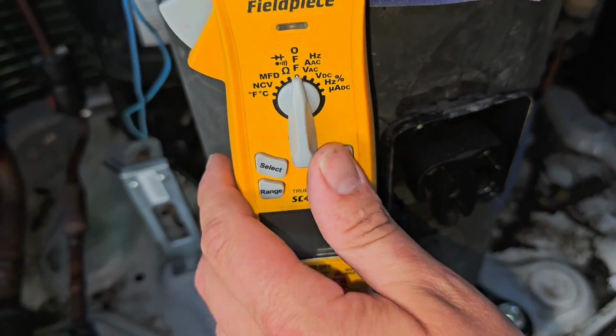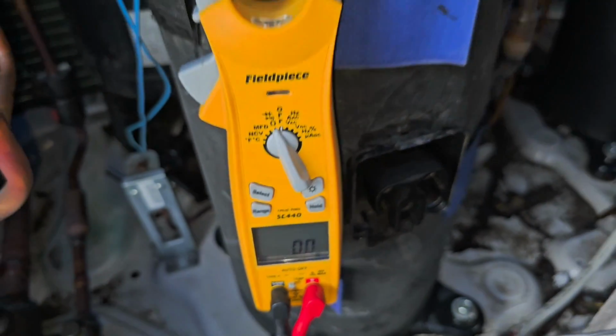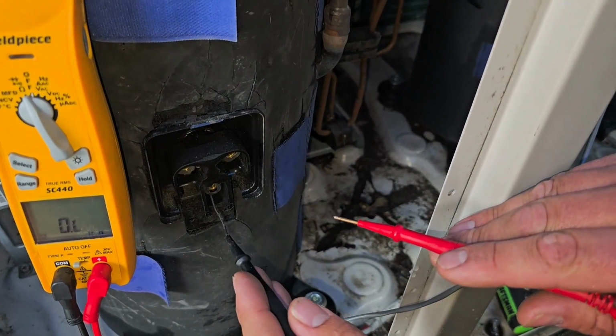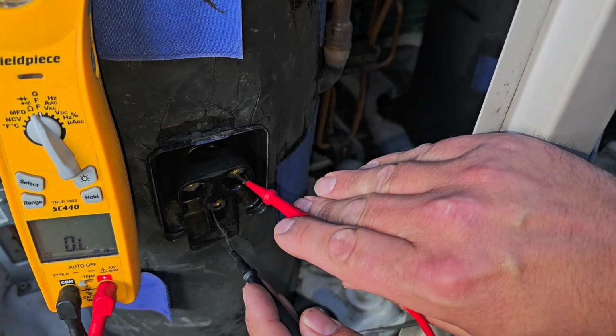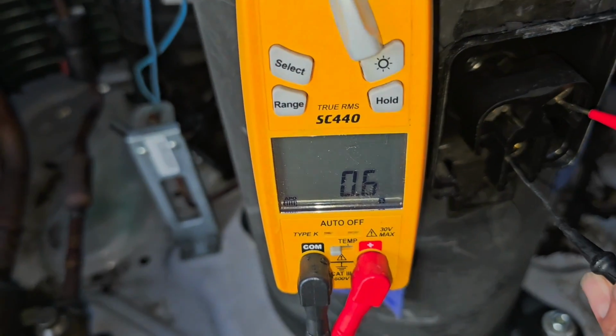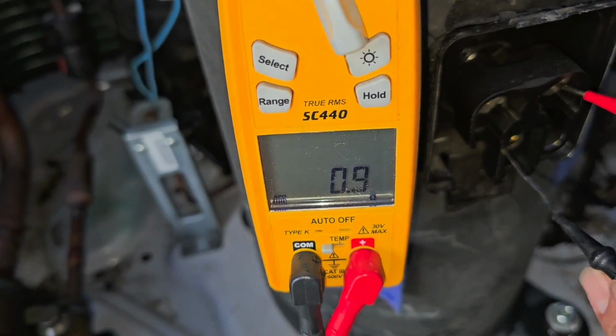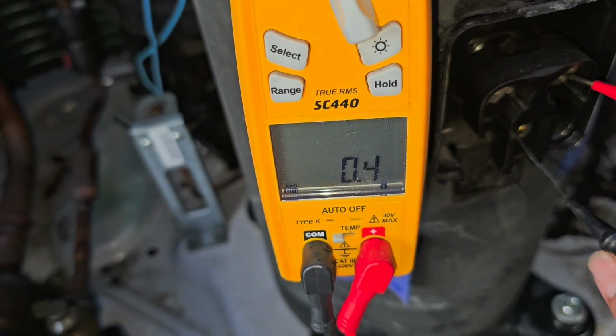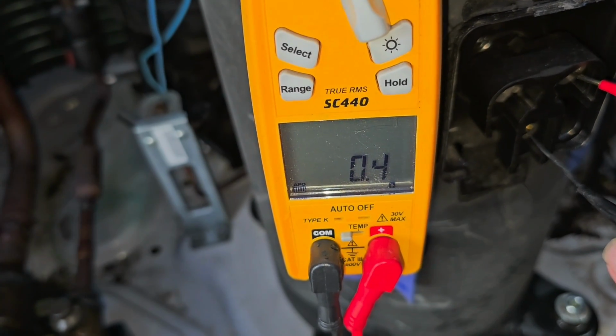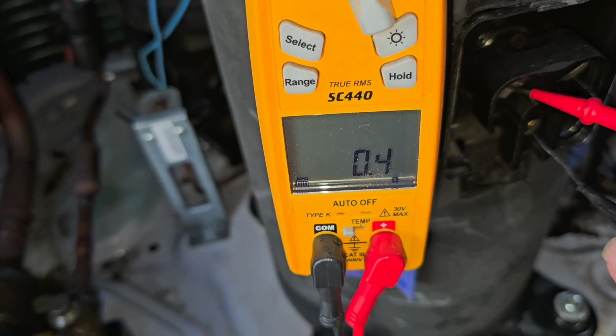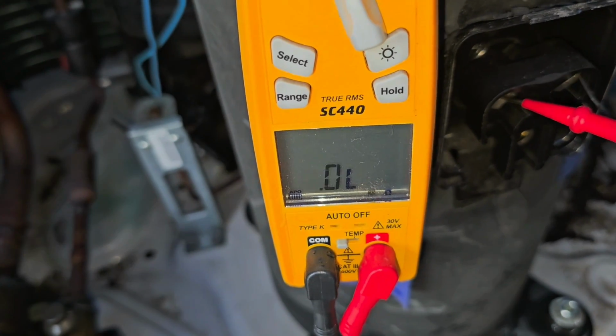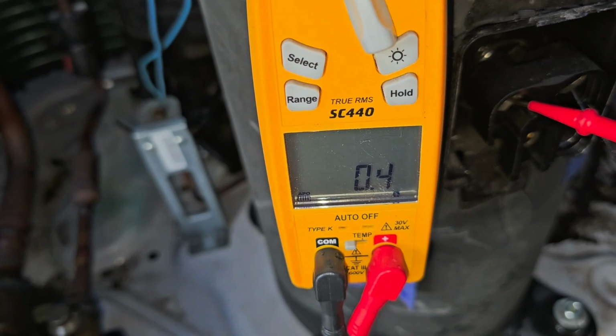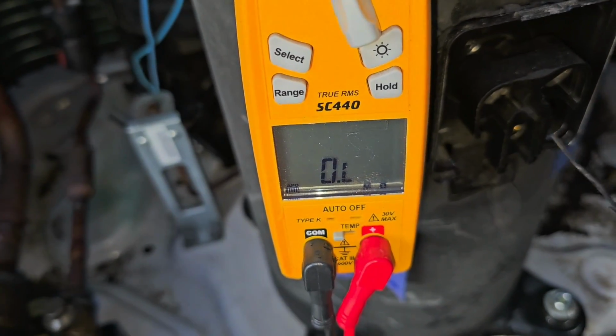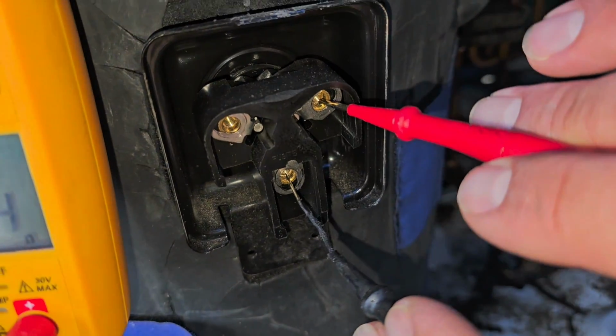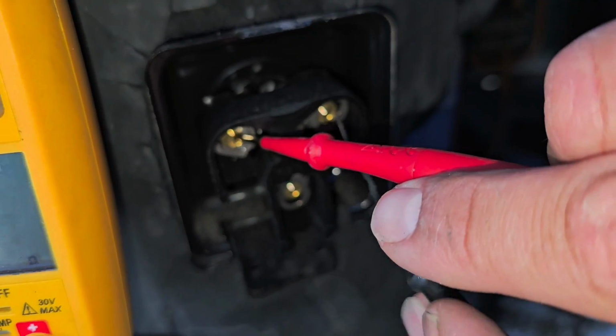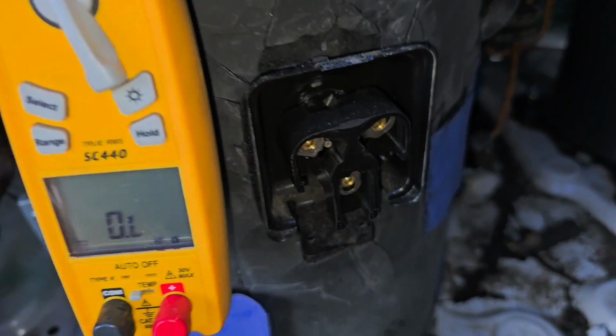Now we're going to check the windings of the compressor. So we're going to turn the meter to ohms, and then we're going to go from each winding to the next. And since it's 3-phase, they should all be the same. Let's make sure we get a good reading. 0.4, 0.4, 0.4. So you saw how I did that? I went from each winding like this, and we got 0.4, and that's less than 2 ohms.